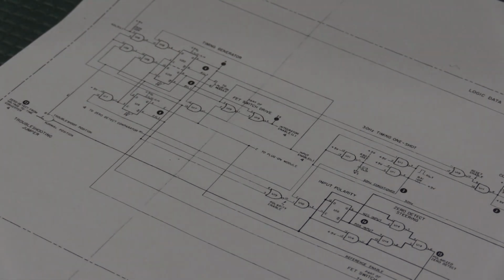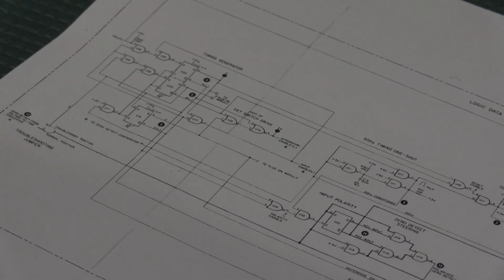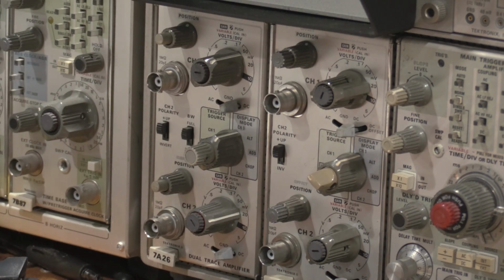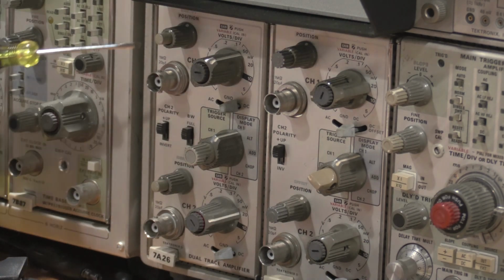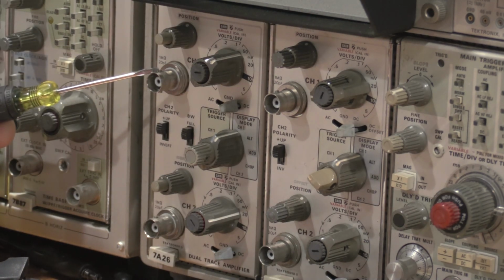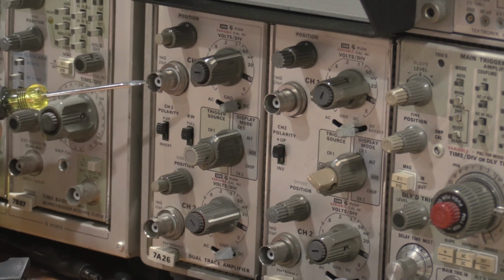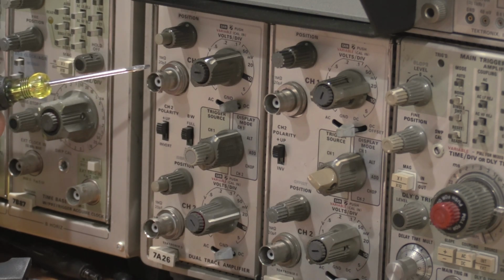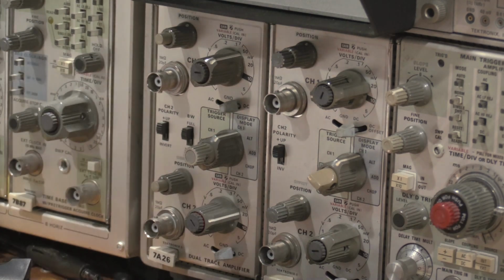So we'll take a look at the front of a scope. On the front of a scope, pretty much every scope, unless it's an isolated ground scope, the barrel of this connector is referenced to earth ground through the chassis, through the electric panel, out to earth. So in a measurement context, the scope is single-ended. So we're taking whatever's on this center pin, and we're measuring it versus what's on ground, which is the outer shield.